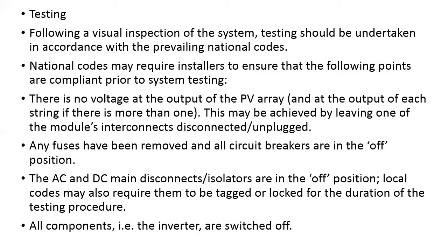So what are the things we have to do? Following a visual inspection of the system, testing should be undertaken in accordance with the prevailing national codes. As I told you, each and every country will have its own national codes, and we have to follow those national codes for the testing of the equipment. The first thing is to check that there is no voltage at the output of a PV array and at the output of each string, if there is more than one.